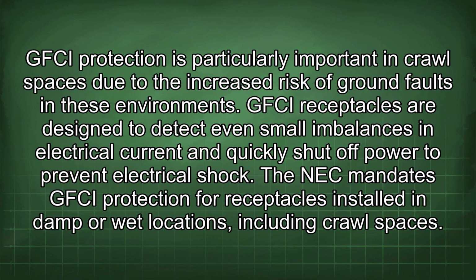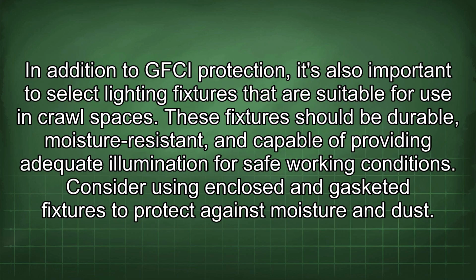GFCI protection is particularly important in crawl spaces due to the increased risk of ground faults in these environments. GFCI receptacles are designed to detect even small imbalances in electrical current and quickly shut off power to prevent electrical shock. The NEC mandates GFCI protection for receptacles installed in damp or wet locations, including crawl spaces. In addition to GFCI protection, it's also important to select lighting fixtures that are suitable for use in crawl spaces. These fixtures should be durable, moisture resistant, and capable of providing adequate illumination for safe working conditions. Consider using enclosed and gasketed fixtures to protect against moisture and dust.